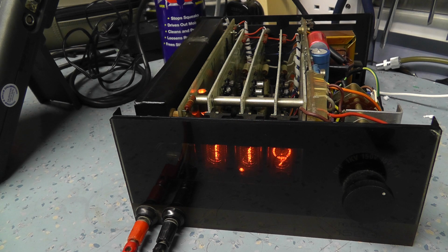Let's go down. Let's go to top range. 1.5 volts. 1.49. So slightly below what it should be. Pretty good. Let's see. 50 millivolts. 0.05. Enter. That's it. And that's a bit low, okay, but this is on the limit of what this sort of meter would be able to respond to anyway.